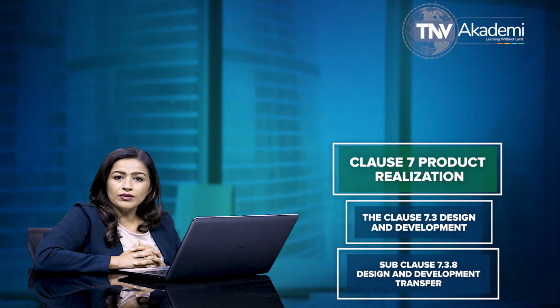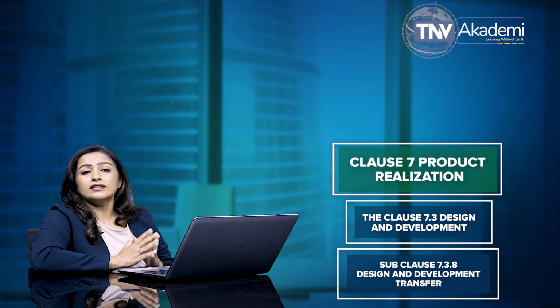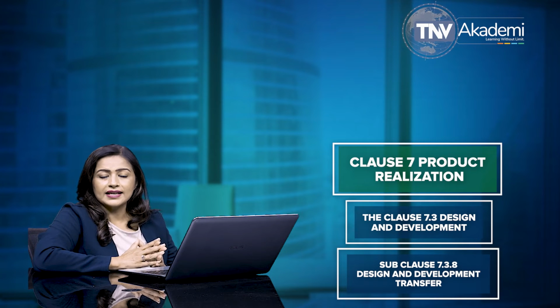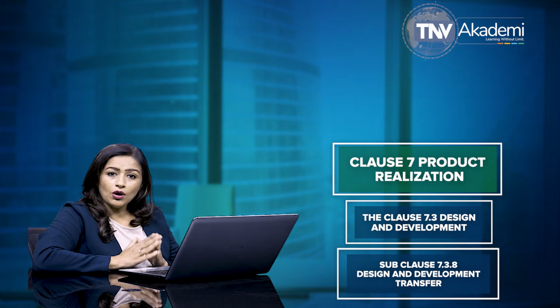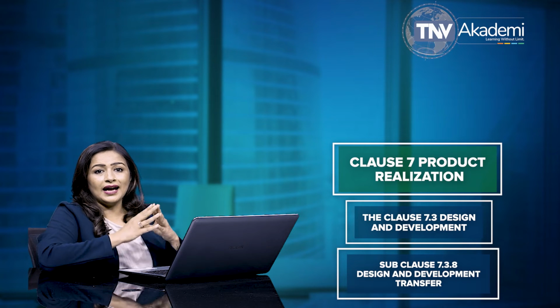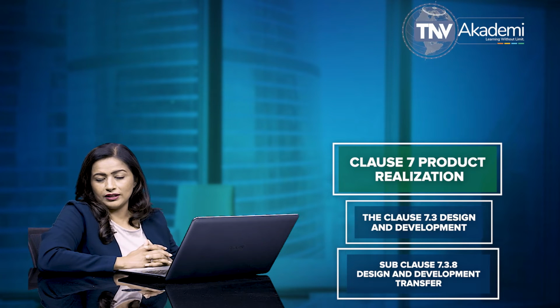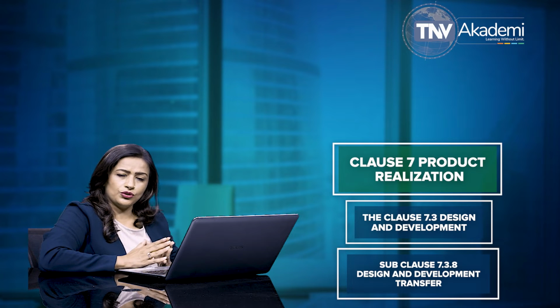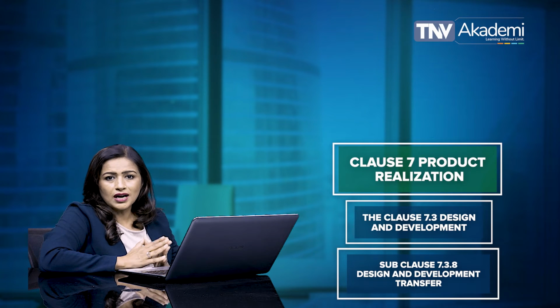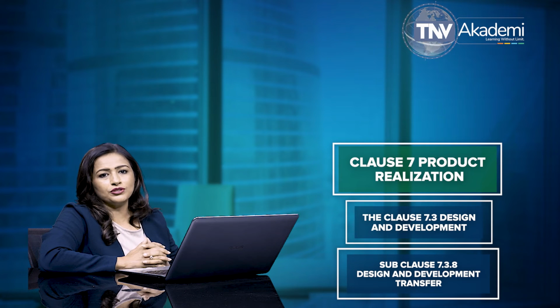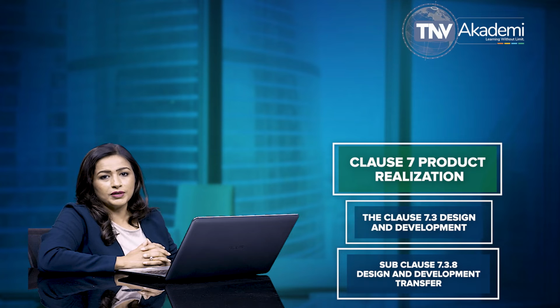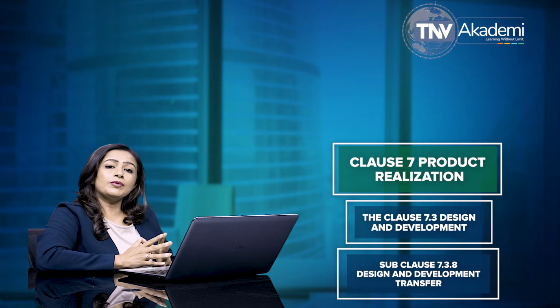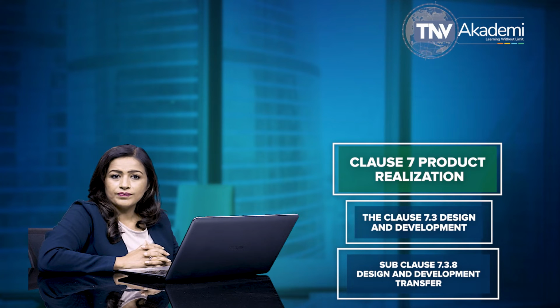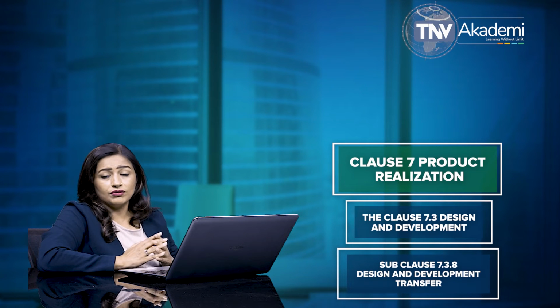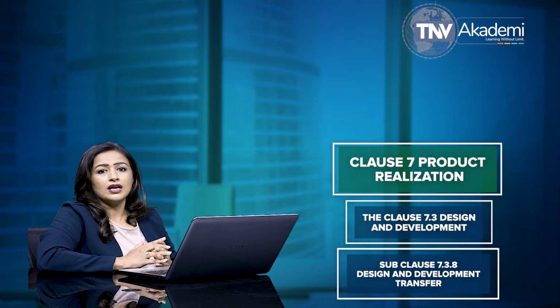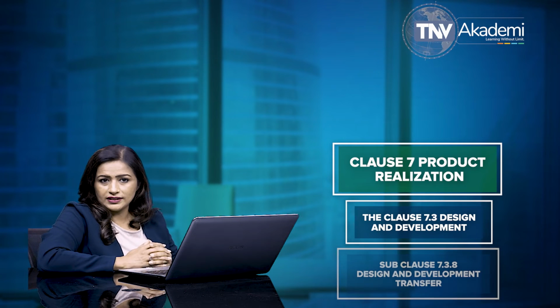This subclause 7.3.8 of ISO 13485 says that the organization is required to document procedures for transfer of design and development outputs to manufacturing. These procedures are required to ensure that the design and development outputs are verified as suitable for manufacturing before becoming final production specifications and that production capability can meet product requirements. This clause also states that results and conclusions of the transfer are required to be recorded by the organization.